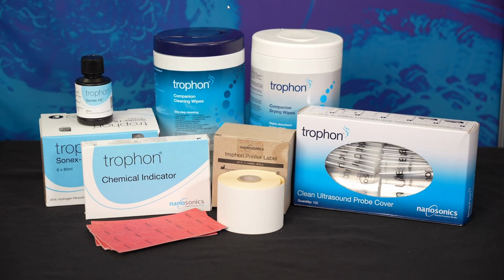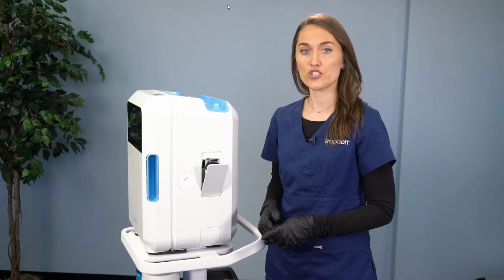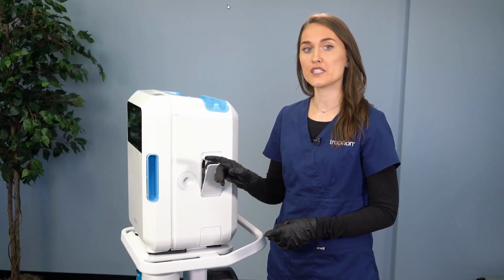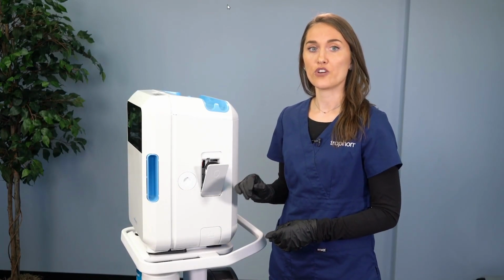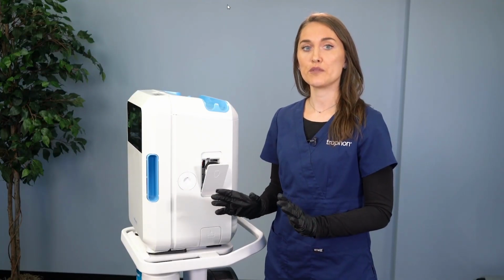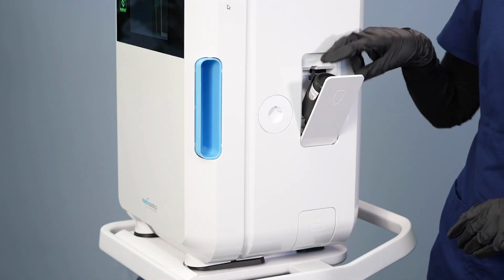Users will be prompted on the LCD screen when the cartridge is empty or it's expired. Please note that the device should not be tilted more than 15 degrees in any direction once the disinfectant is loaded. Sonex cartridges must be stored in an upright position to prevent leaking. If the cartridge is empty, you'll be alerted on the display screen. Put on a fresh pair of gloves and follow the screen prompts to scan in and load a new cartridge.